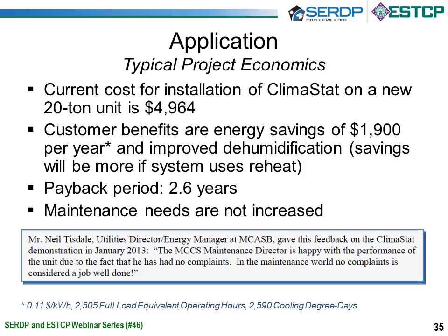Application example: the current cost for installation of ClimaStat on a new 20-ton unit would be a little under $5,000. The benefits for specific climates, of course, change depending on climate. Let's say it is $1,900 per year. This would be for a temperate climate and improved dehumidification. Payback period, 2.6 years. Maintenance needs are not increased.